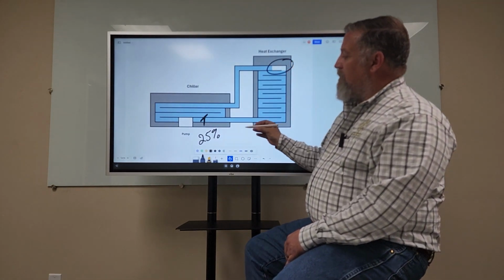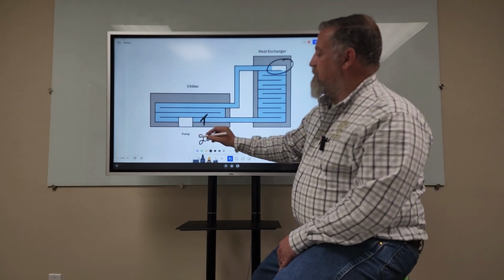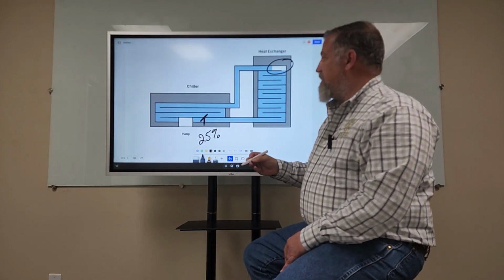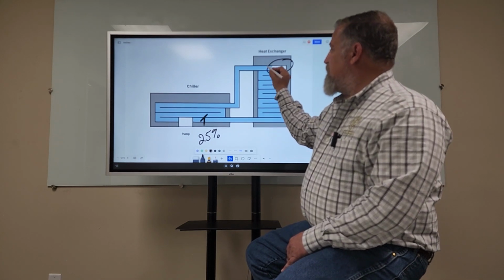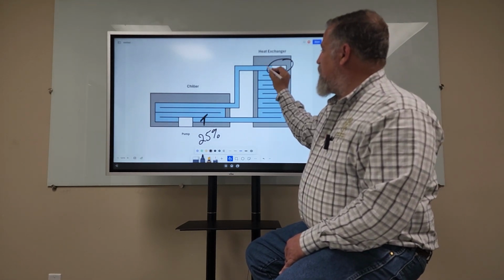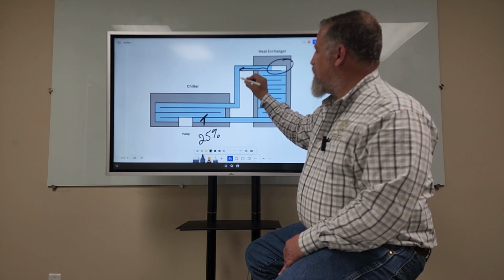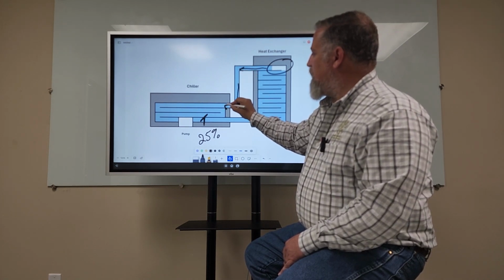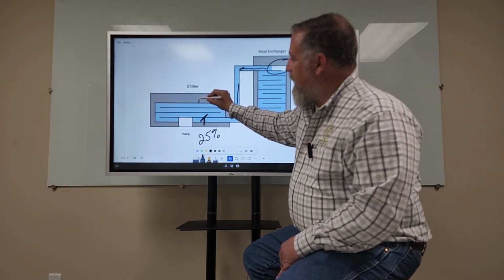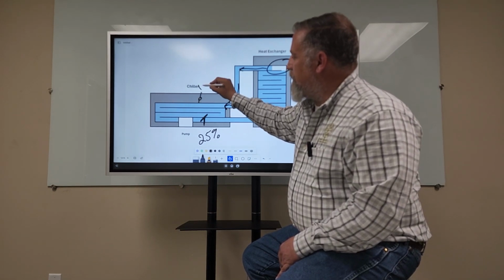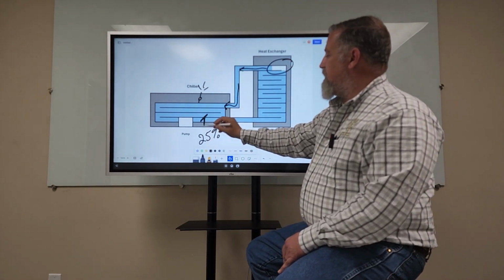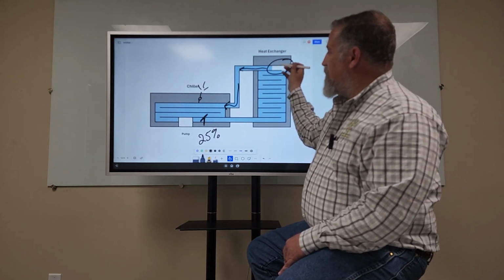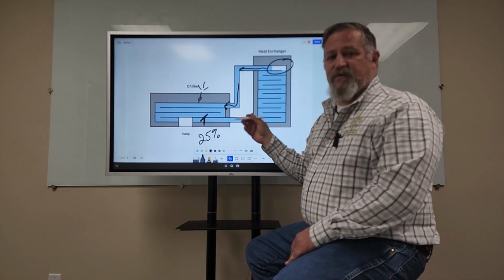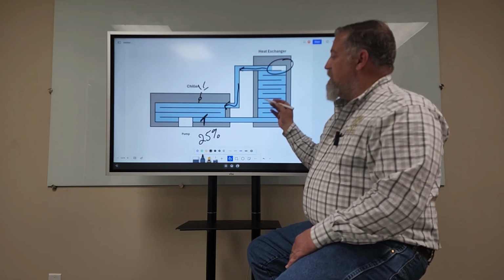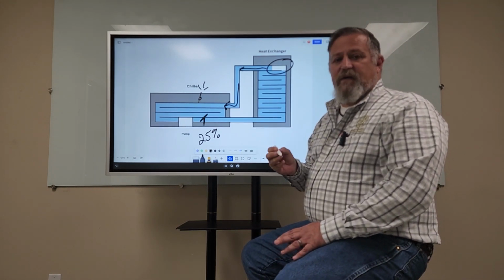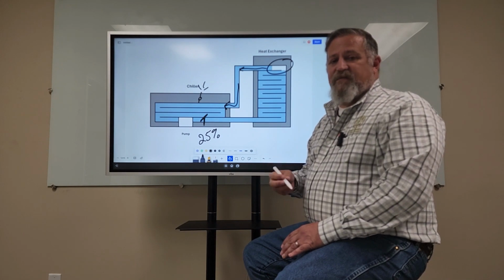Then we're going to power on our unit, and we are only going to turn the pump on for several seconds. Okay. What that's going to do is it's going to establish flow, and it's going to push this air pocket to an area where we hopefully have a ball valve where we can vent that off. And by reducing that down, that's not going to force us to make this pocket into micro bubbles that are going to circulate throughout the system. So now that we understand the theory about it, let's go outside and let's take a look at it on one of our chillers that we have set up outside.